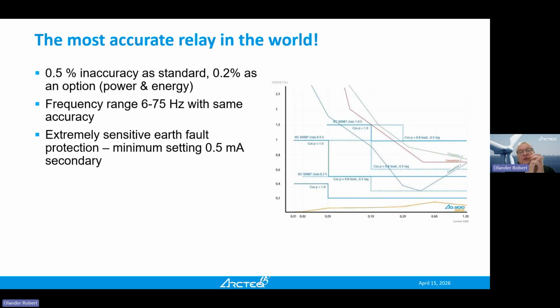Okay, and now we come to the most accurate relay in the world. So I think still we are the only relay manufacturer with a device on the market which meets the accuracy of 0.2% on power and energy. So basically you can use this for metering. Of course, very rarely it's used as a metering device, but it can be easily used for reference metering. You can compare your billing meters to your customers with the values you get from the relay on the substation to make sure that everything is okay. And so reference metering is something that can be used.